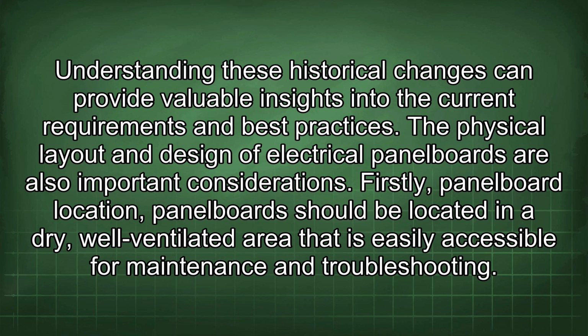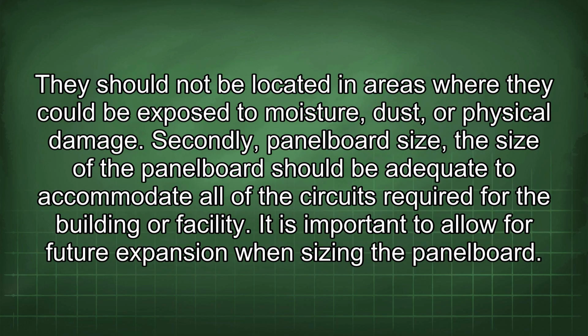The physical layout and design of electrical panel boards are also important considerations. Firstly, panel board location. Panel boards should be located in a dry, well-ventilated area that is easily accessible for maintenance and troubleshooting. They should not be located in areas where they could be exposed to moisture, dust, or physical damage.